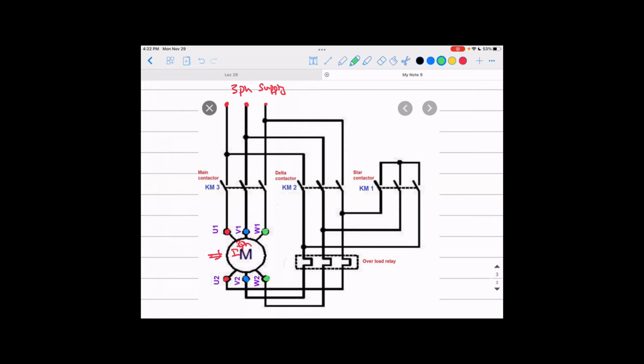Okay, so for this you have the main contactor of the machine. Remember the contactors when you talked about the direct on line? The contactor is just basically a 3-phase switch that can close or open, and that can be remotely controlled, so you can switch it on or off from your control room, actually in your industrial facility. So that's the main contactor that's connected to the motor, like the circuit we just investigated for the direct online method. But here we need 2 other contactors. One we call the delta contactor, and another one we call the star contactor.